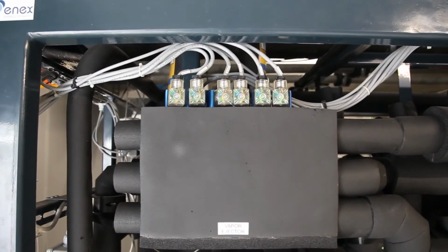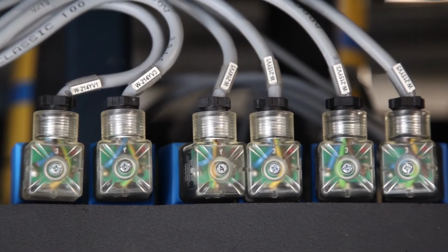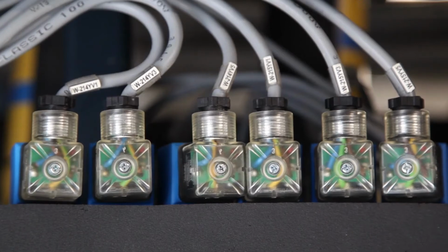ejector. There are different types of ejector installed in this system. We have a low pressure lift ejector, which is responsible for the air conditioning part, and we have a high pressure lift ejector, which is responsible to support the medium temperature cabinets and push some of the gases towards the parallel compressors to support this more energy efficient way to operate, especially at high ambient temperatures.